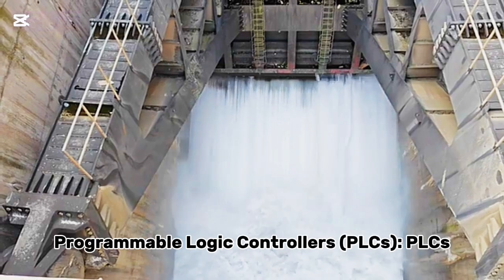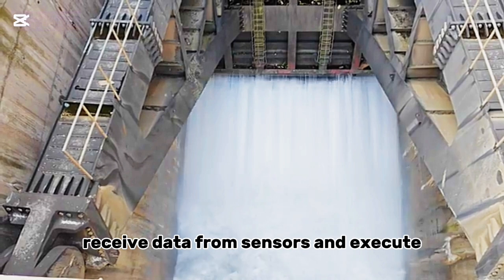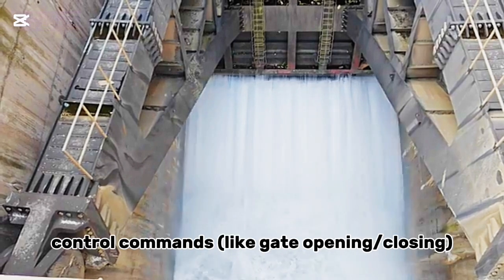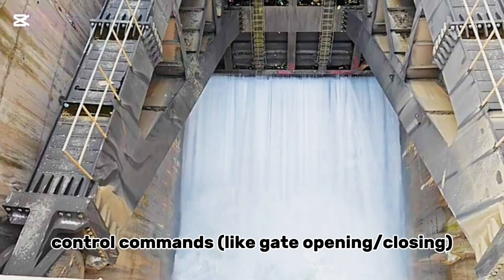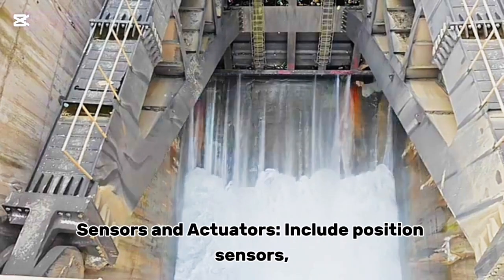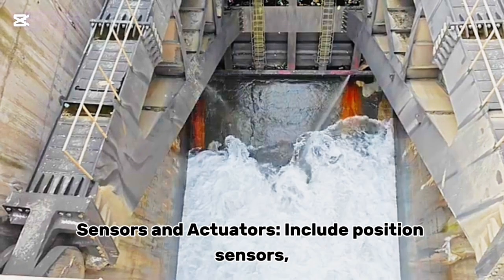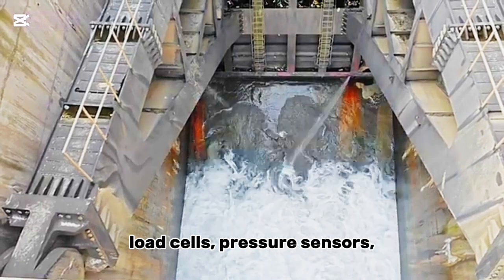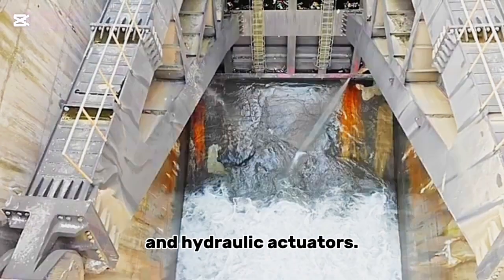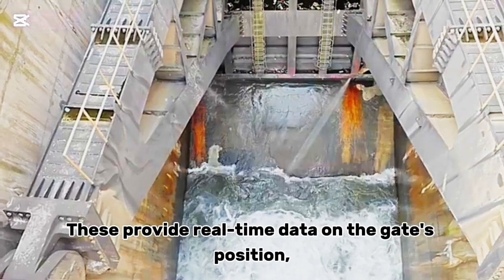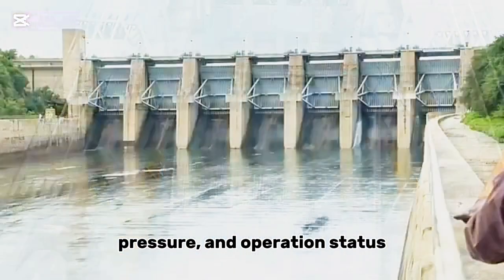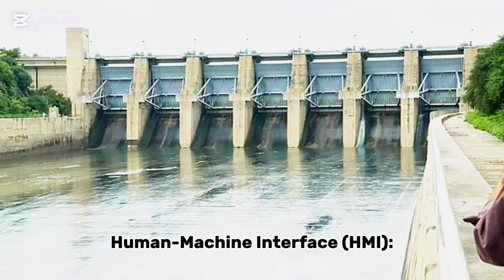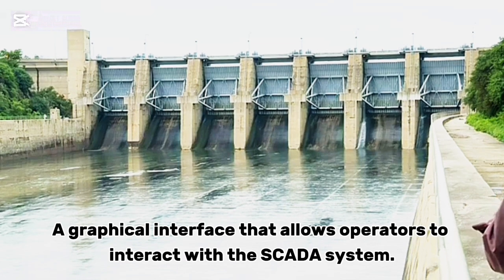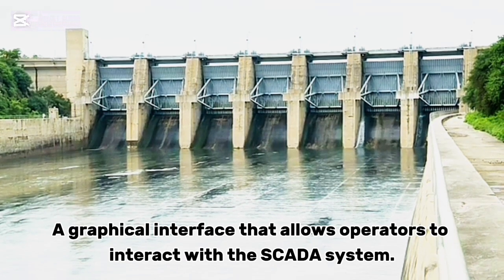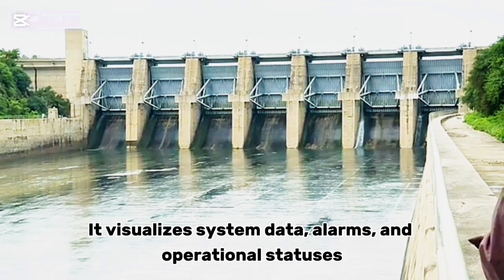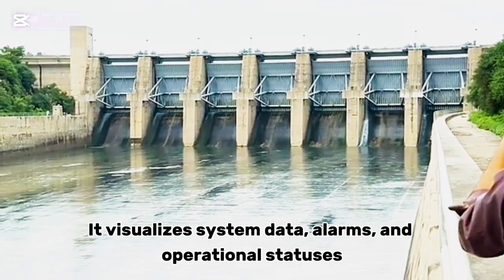Programmable logic controllers (PLCs). PLCs receive data from sensors and execute control commands like gate opening, closing, based on pre-programmed logic. Sensors and actuators include position sensors, load cells, pressure sensors, and hydraulic actuators. These provide real-time data on the gate's position, pressure, and operation status. Human-machine interface (HMI), a graphical interface that allows operators to interact with the SCADA system. It visualizes system data, alarms, and operational statuses.